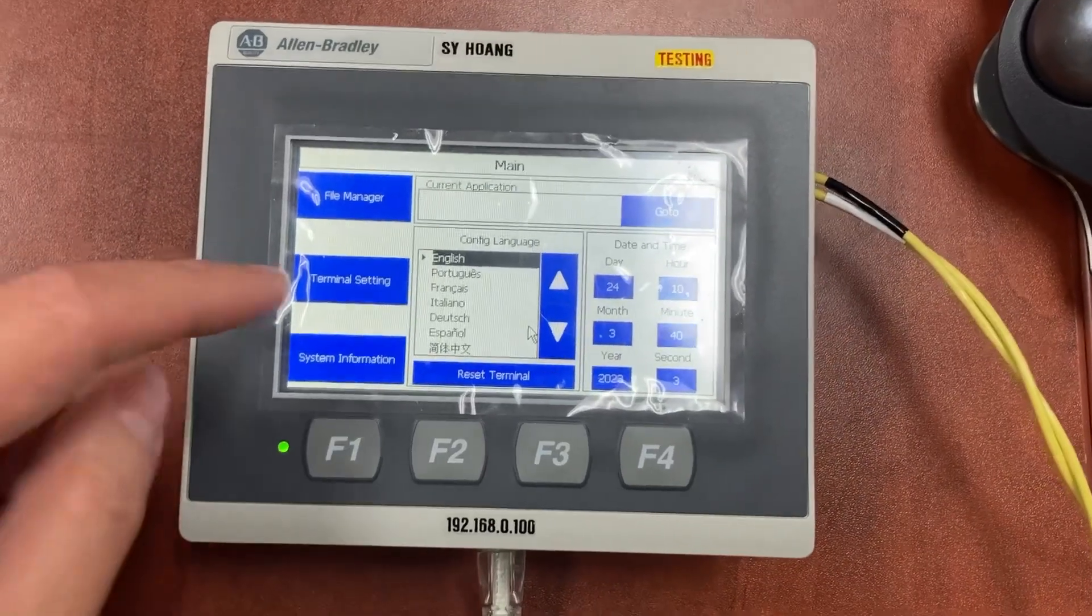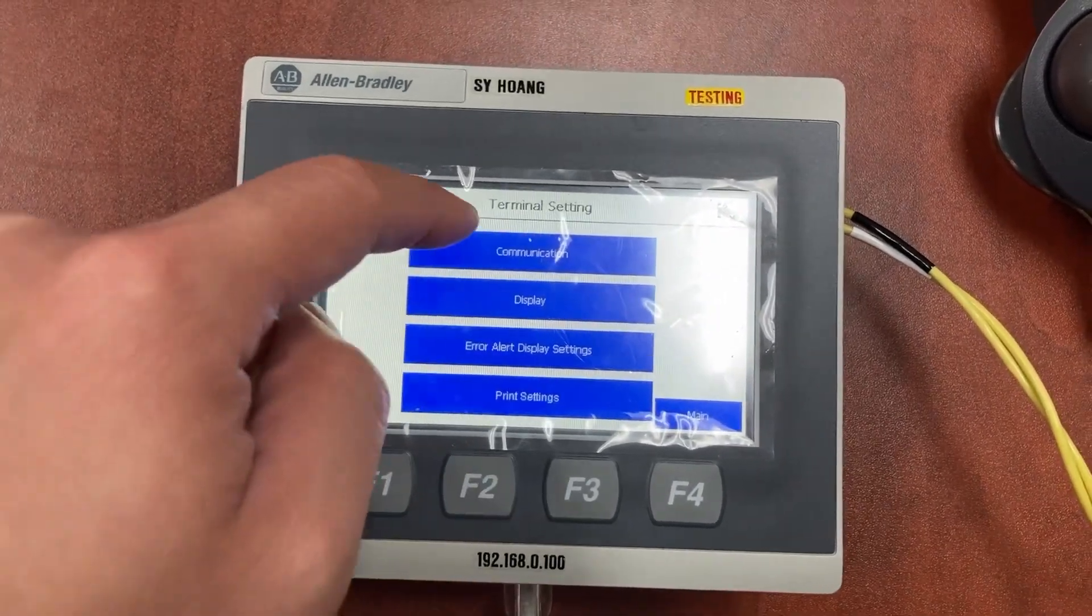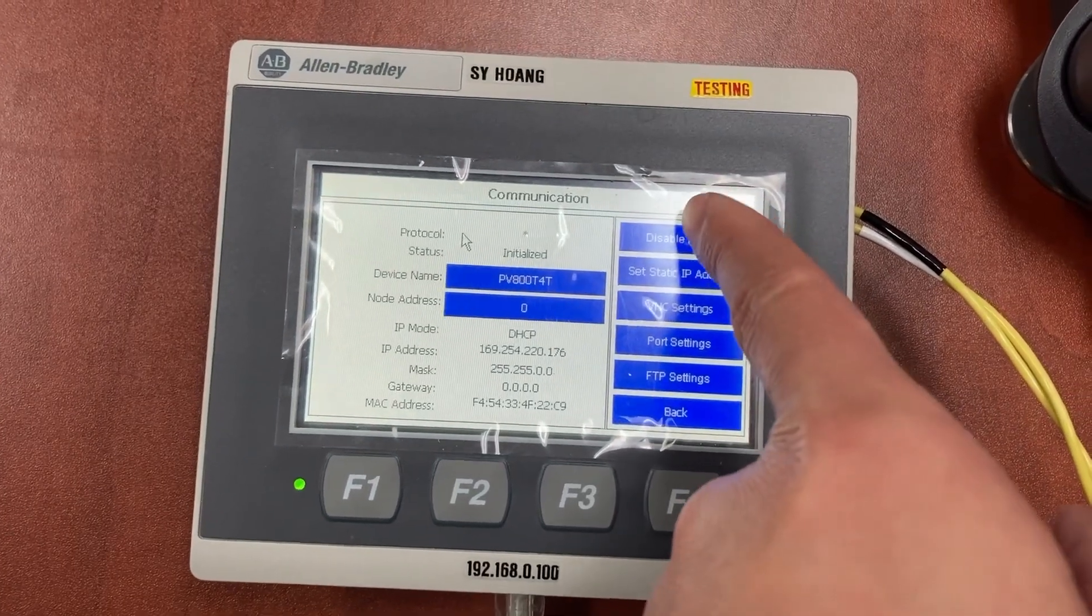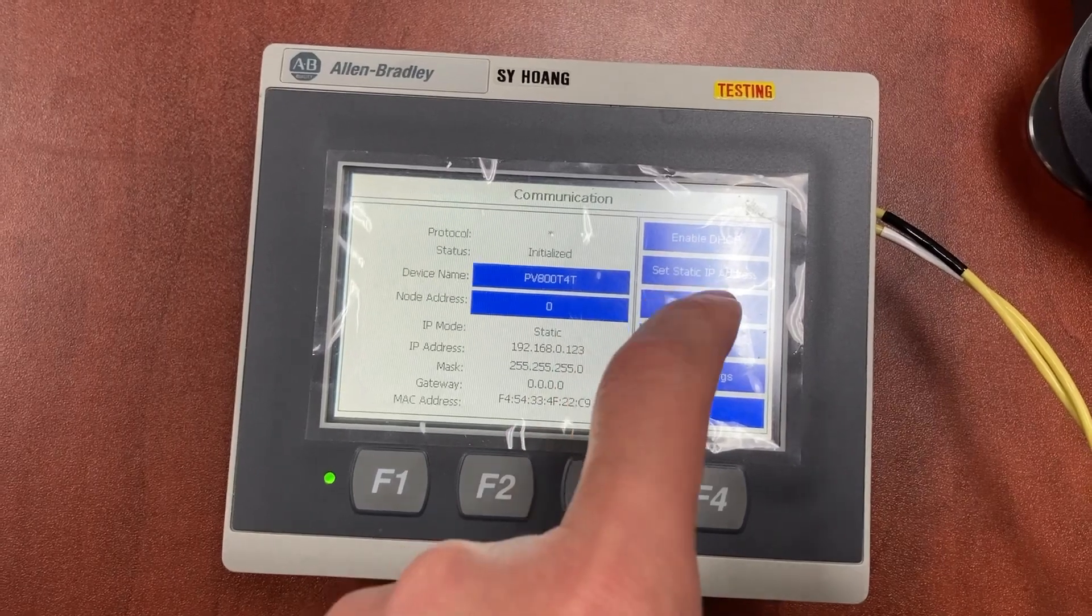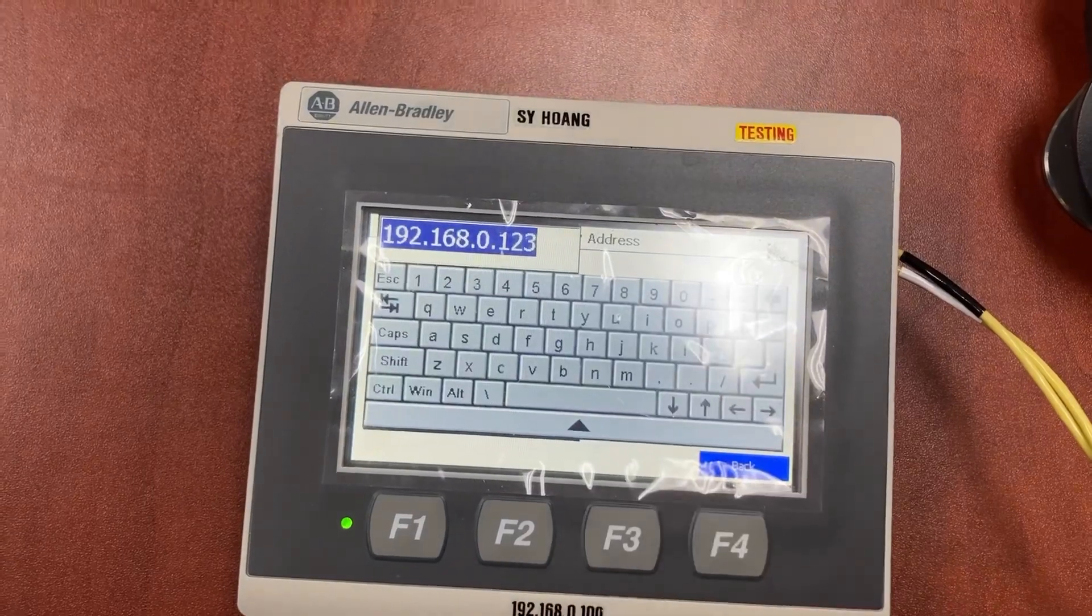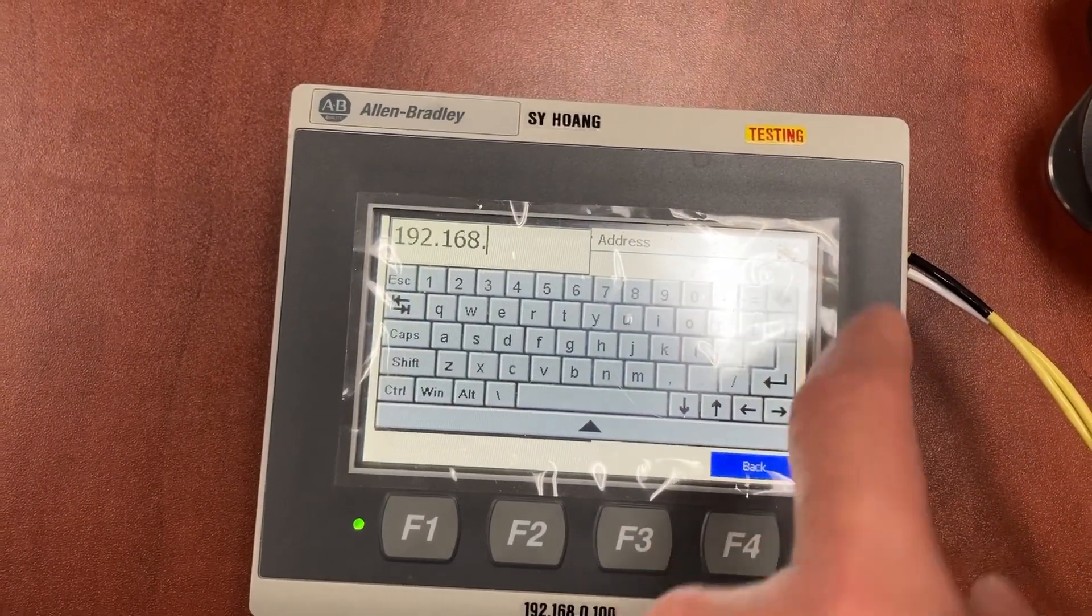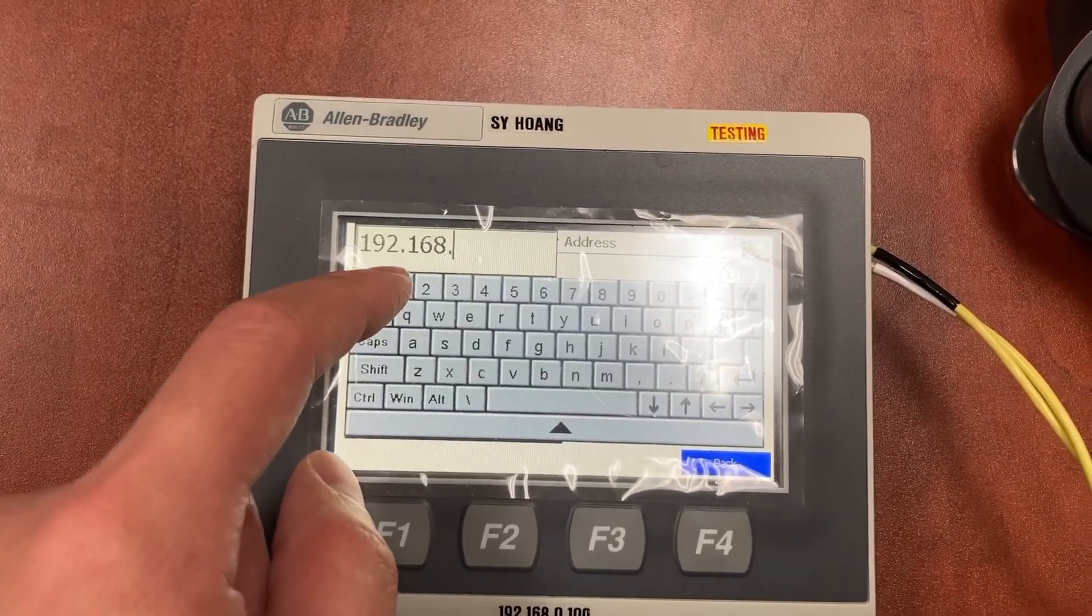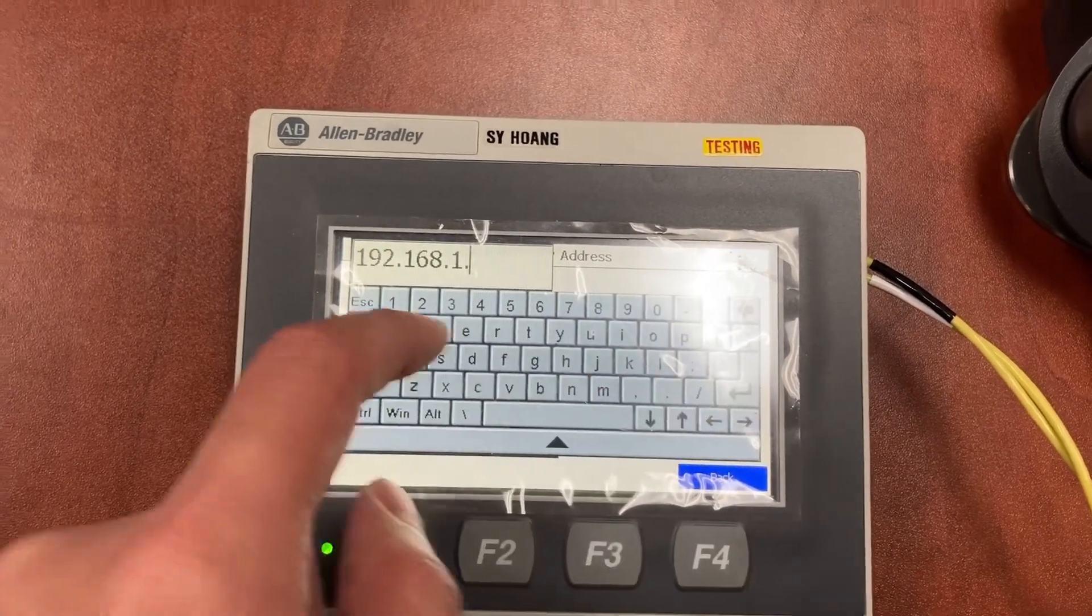So we will need to go to terminal settings, communication, disable DHCP. It will need to be set to a static IP address. It will be 192.168.1.2.